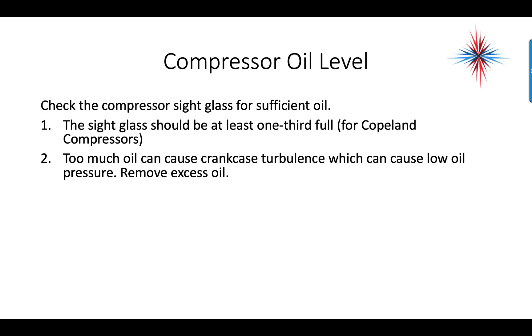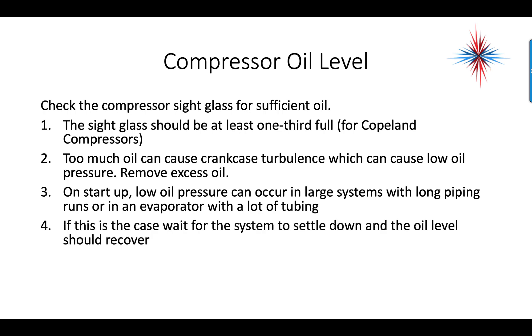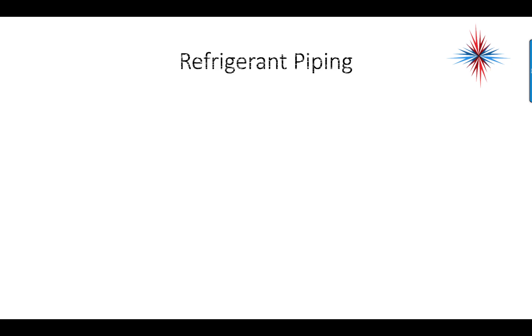This should be checked with the system off. On startup, low oil pressure can occur in large systems with long piping runs or in an evaporator with a lot of tubing. If this is the case, wait for the system to settle down and the oil level should recover. If the system is new, you must wait 24 hours after startup to add any oil, because oil does migrate through a refrigeration system in transit.